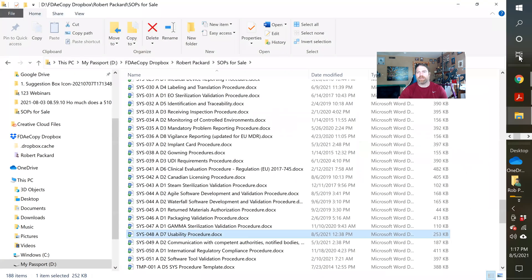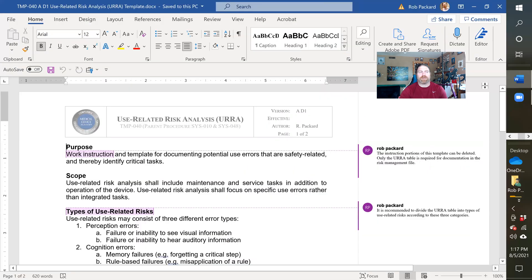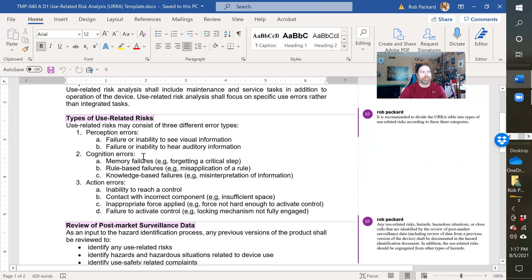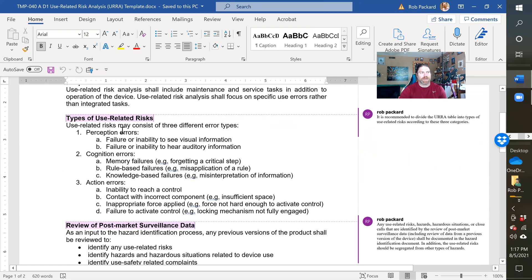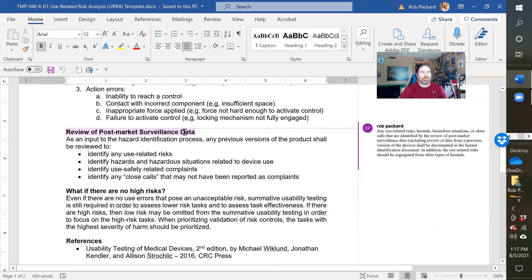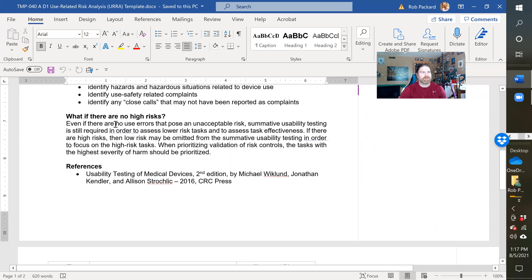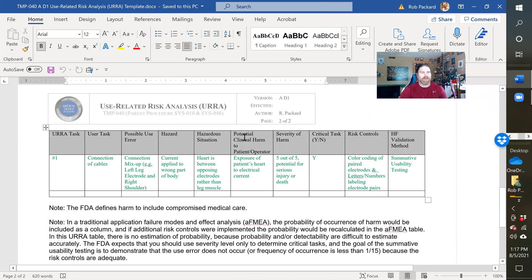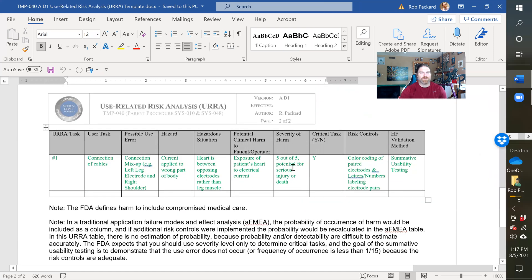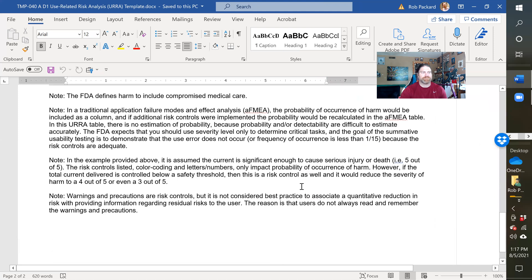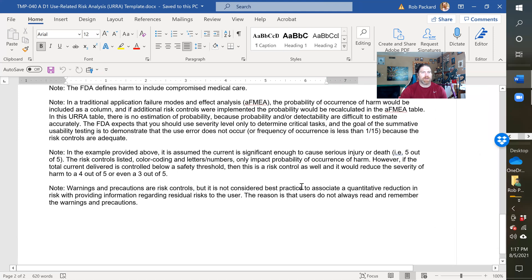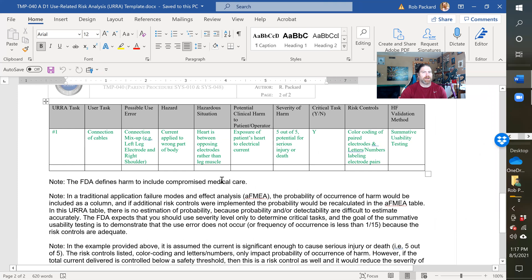And then the last thing that the FDA also wants to see is this, the URRA or use related risk analysis, and we provided a template for that. So types of use related risks, post market surveillance data. And here's the actual format so we've actually got it as a table there that you could duplicate and add rows to, or you can put it in an Excel spreadsheet. And we talked a little bit about the scoring here. So that's the end of what you get when you purchase this procedure.